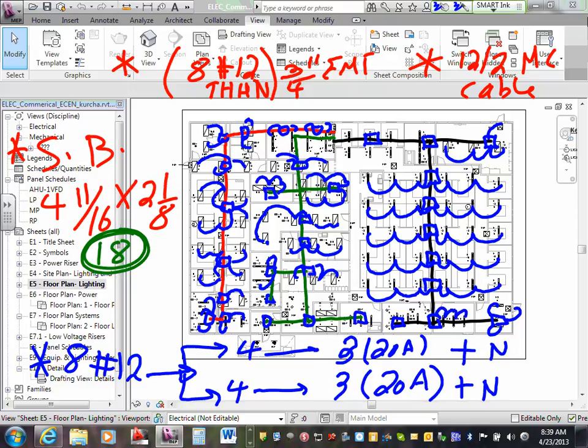Same thing. I bring a conduit here, and I picked up these lights with an MC cable. So I covered this area. Then I went with another conduit system. I threw it here. I picked up with a J box. Every area I threw a J box, at least one J box, and I moved all the way through. I came to this area, guys. The same thing. I put my conduit system, picked up a J box, loop them into the J box.